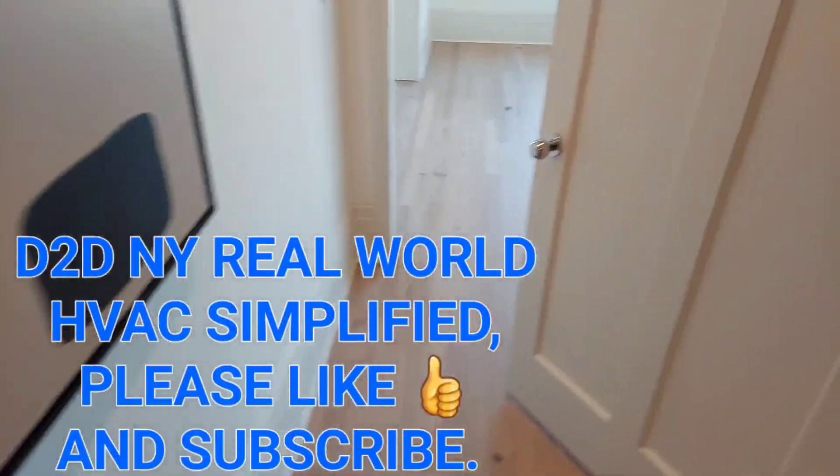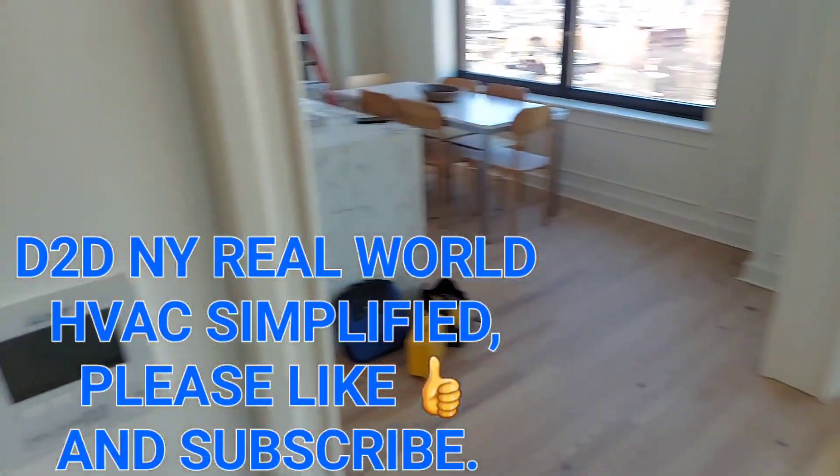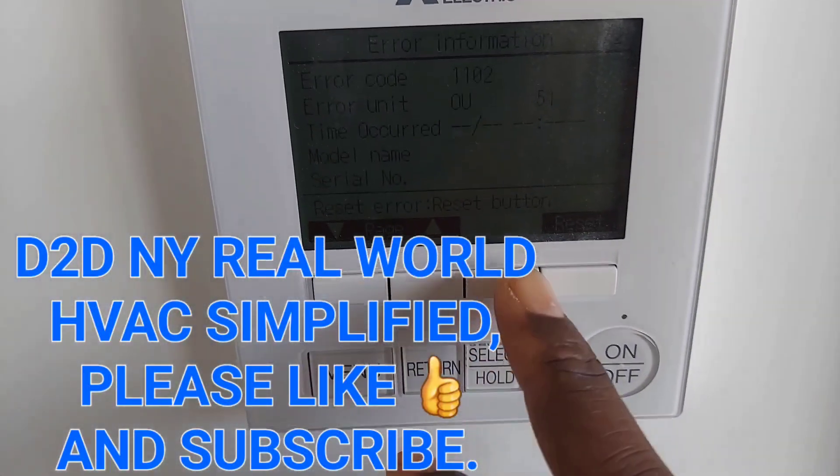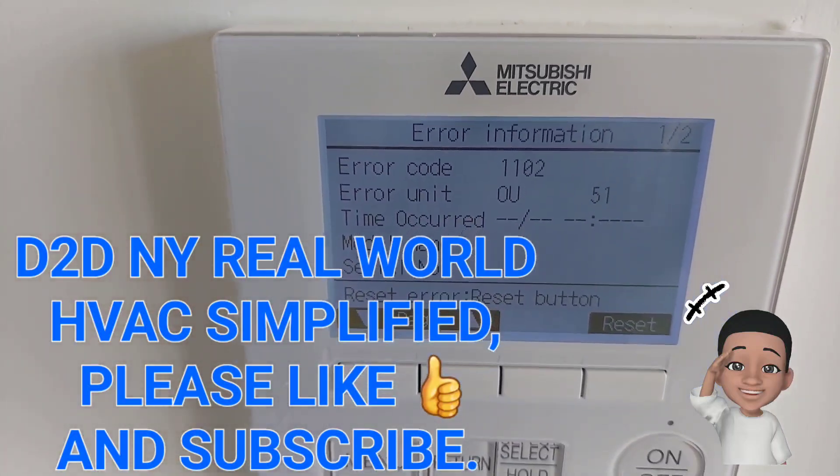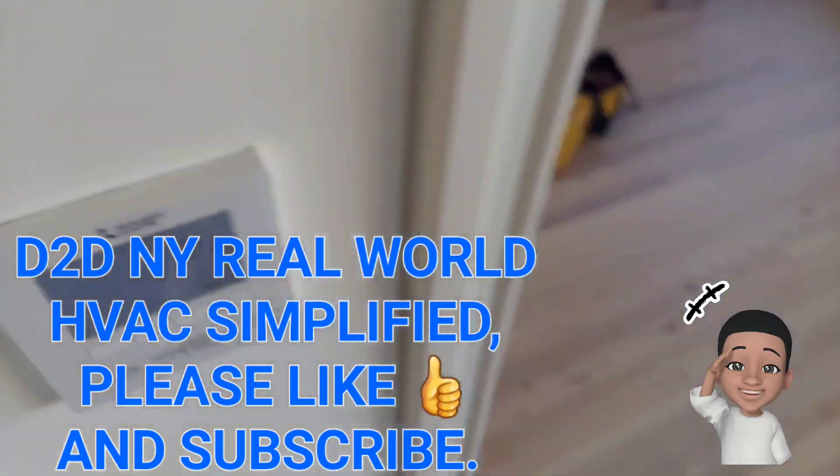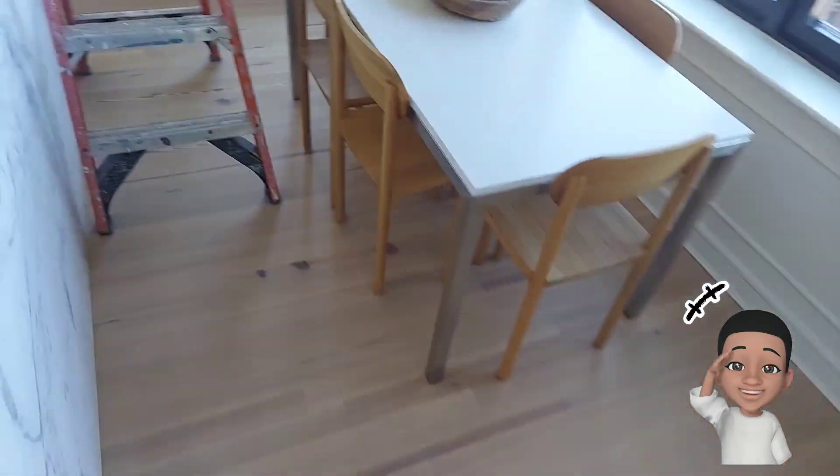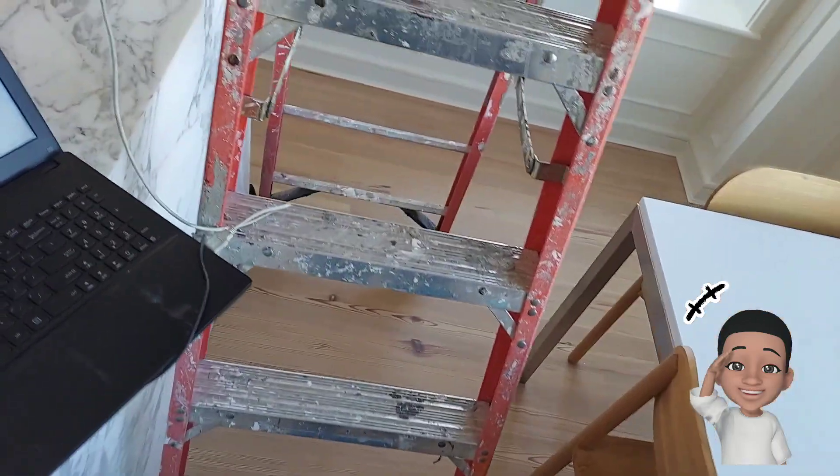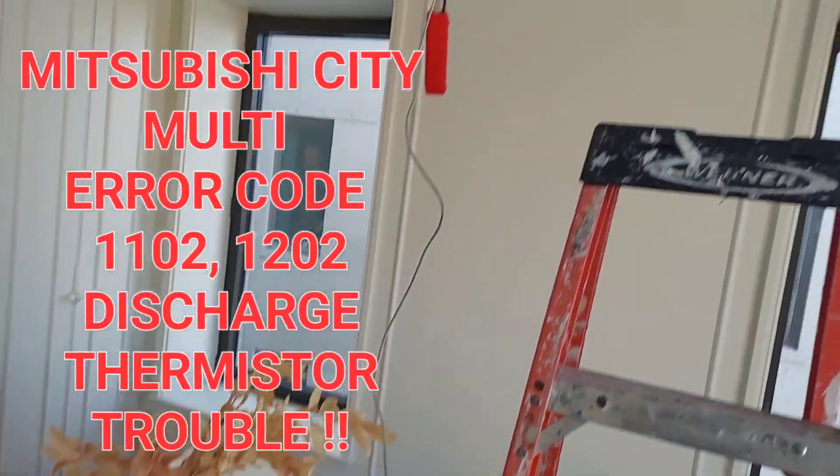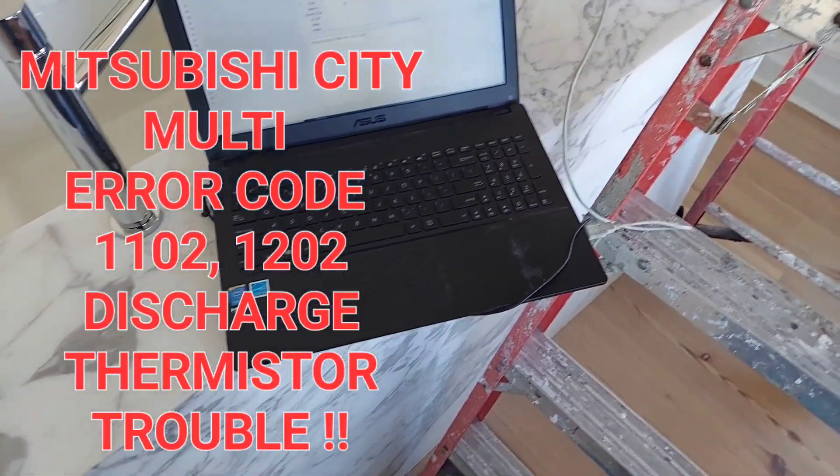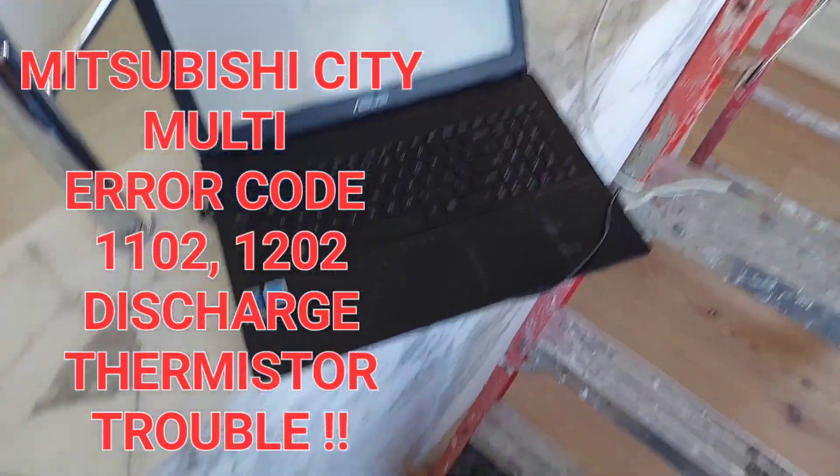D2DNY Real World HVAC Simplified. In this video, got a Mitsubishi City Multi with an 1102 error code. I believe that is a discharge thermistor or discharge pipe's too hot error. As you can see, I already got my, I'm by the indoor unit and I already have my computer hooked up. Let's go up and show you that.